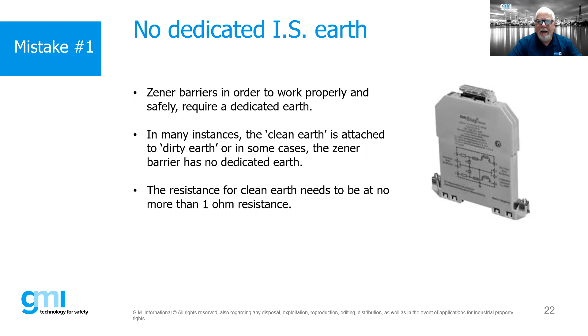Excuse me, Bob. Here we have a question, which I simplify: how do you ensure the clean earth is well connected and working? Right, that's a great question. Typically, it's common practice, and this is spelled out within the dash 14 standard, and I believe it's also referenced in dash 25 as well. We might have two earthing connections, and the way you would test it is a resistance test between the connection points.